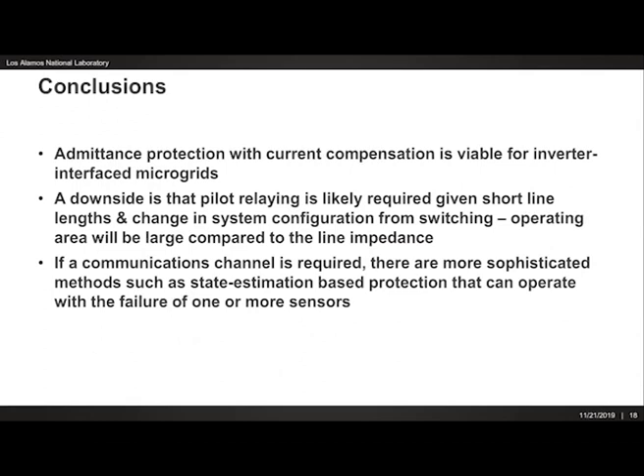Now, there are still potential issues with this protection method. In particular, the most significant issue is in a relatively small microgrid, the line impedances are going to be negligible compared to the source impedance of the inverter. So this means that what I had to do was set the operating region for the admittance protection to be very large. So that's why I'm using the term admittance protection as opposed to distance protection, because I can't reliably estimate where on the line the fault is. And this means that in order to maintain protection coordination, I'm dependent on using pilot relaying. And if the pilot relaying fails, then I'll end up with an outage area that's greater than necessary.